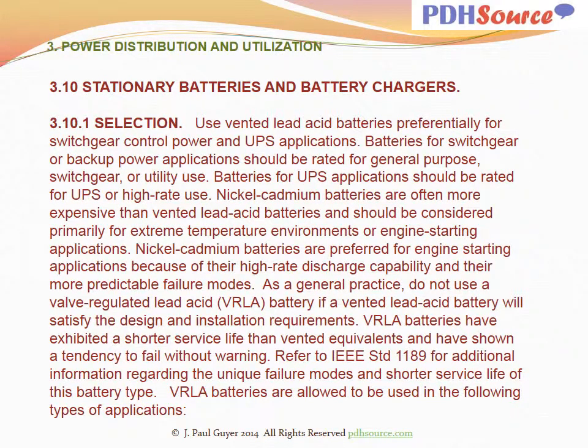With regard to stationary batteries and battery chargers, their selection: use vented lead-acid batteries preferentially for switchgear control power and UPS applications. Batteries for switchgear or backup power applications should be rated for general purpose switchgear or utility use. Batteries for UPS applications should be rated for UPS or high rate use. Nickel-cadmium batteries are often more expensive than vented lead-acid batteries and should be considered primarily for extreme temperature environments or engine starting applications.